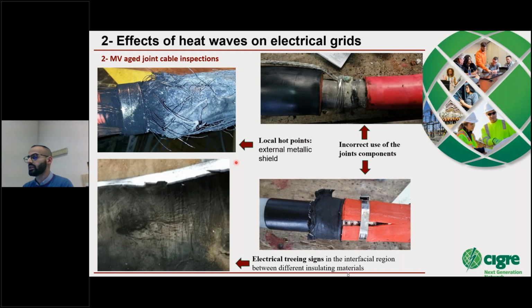For example, in the top left side we can see an opened joint that was subjected to a failure. We can see that this failure started from the point of contact between the cable metallic shield and the joint metallic shield.